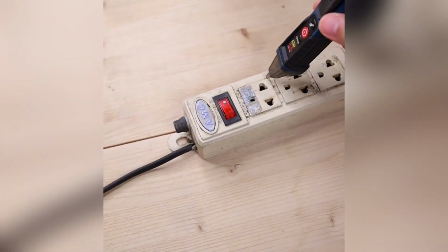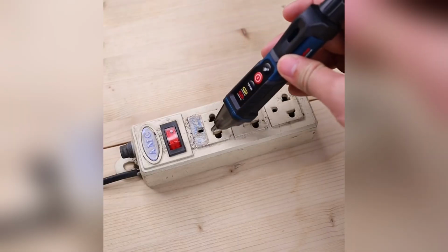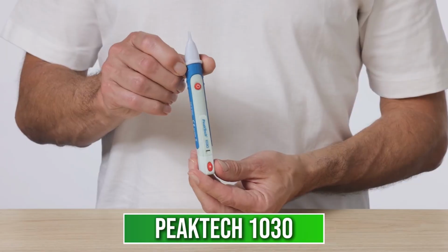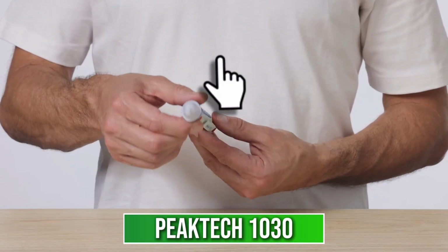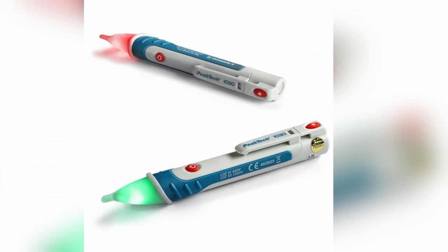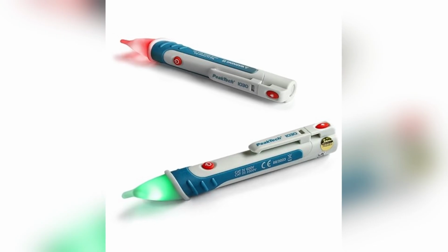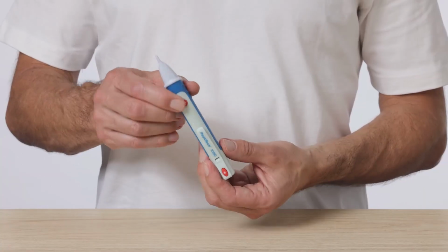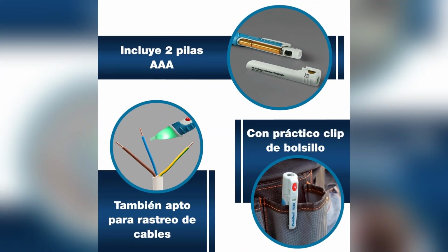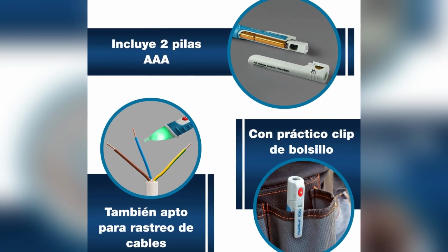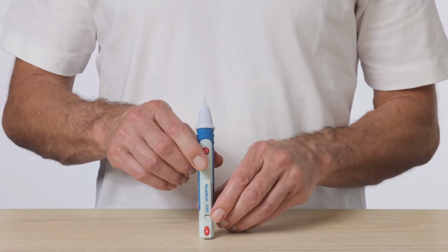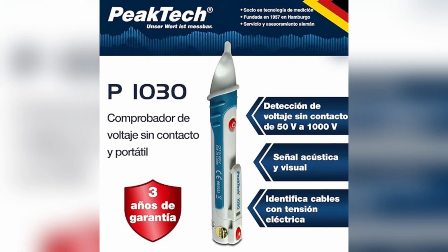And here comes the one that breaks the pattern, because its greatest strength looks exactly like a flaw. The PeakTech 1030 runs against the entire market. It only picks up AC from 50 volts upward, with no high sensitivity mode and no menus. Twin molded housing with reinforced insulation, a torch, light, and sound alerts. Cat3 at 1000 volts and Cat4 at 600. That's your lot. So why is that good?